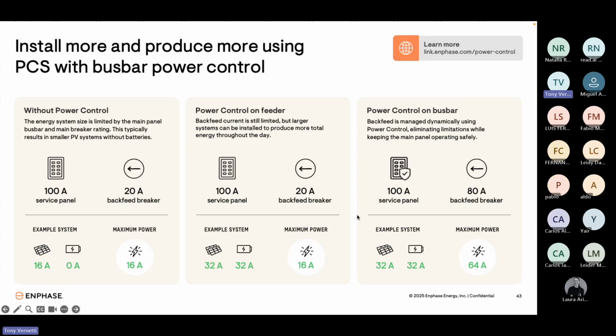Now on the far right, we have our latest power control technology, called power control on bus bar. This refers to the bus bar of the main panel, and we can control how much electricity is flowing through that bus bar. If it ever becomes potentially unsafe, we can turn down the power output of the battery and even the solar system to ensure that panel is always safe. Because we have that granular level of control, we can install a much larger system and still know it's going to perform well and be safe.